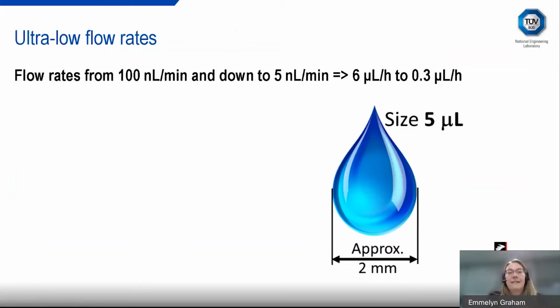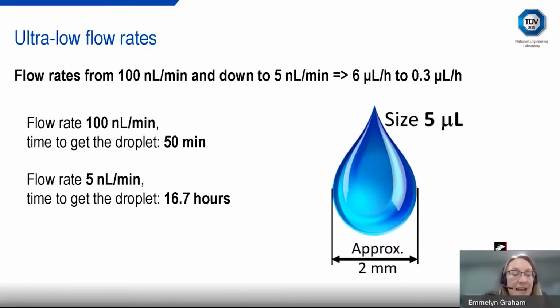So for ultra-low flow rates, we are looking at flow rates from about 100 nanoliters per minute down to 5 nanoliters per minute. And this is tiny, tiny amounts. So if you imagine a drop of liquid and say that the diameter of that drop is about 2 millimeters, to then achieve a flow rate of 100 nanoliters per minute, the time to develop that drop size would take 50 minutes. And if you're down at 5 nanoliters per minute, the time to develop that drop would actually take you over 16 hours. So it gives you an idea of how difficult it is to try and develop these techniques and get very, very low uncertainties for these ultra low flow rates.